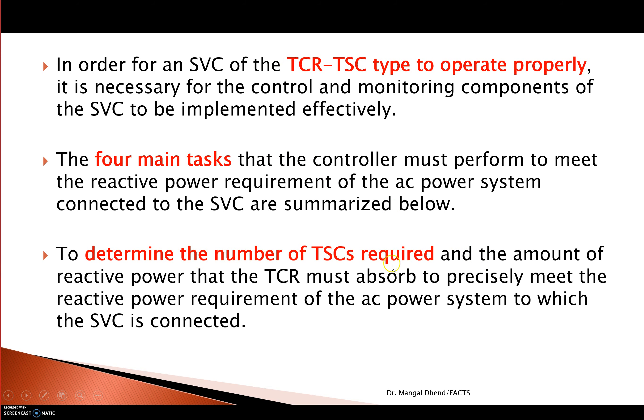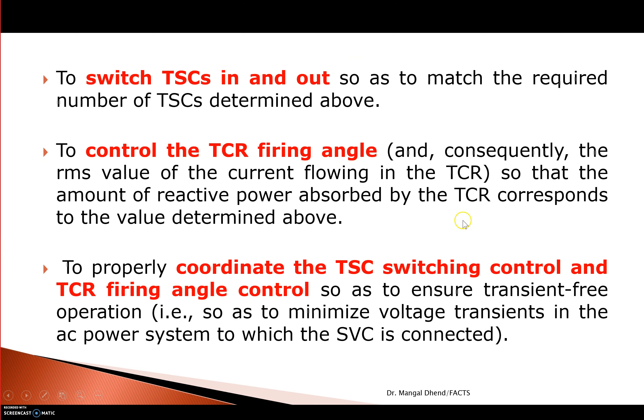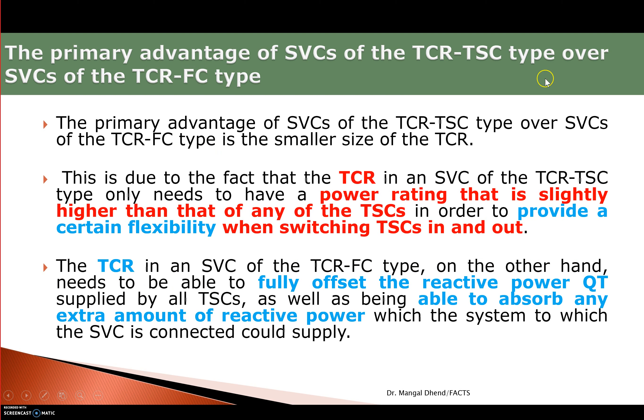The number of TSC branches needed is found from the controller — if total required is 40 KVAR and each TSC is rated at 10 KVAR, then four banks are needed. The TSC branches can be switched on and off, which was not available in TCR-FC. Then the TCR firing angle is determined, and coordination of both TCR and TSC control is required. That concludes the discussion on TCR-TSC. Advantages and disadvantages will be covered in the next session.